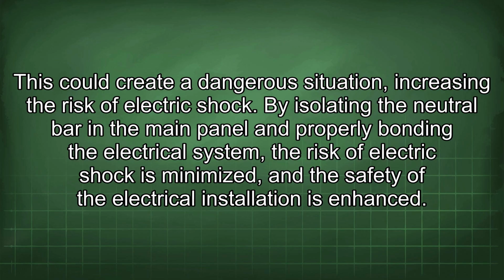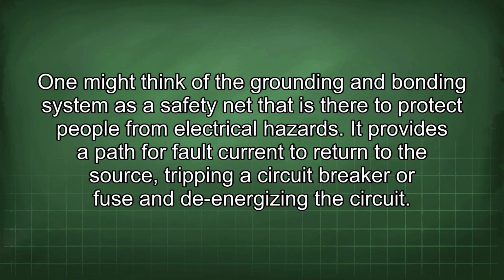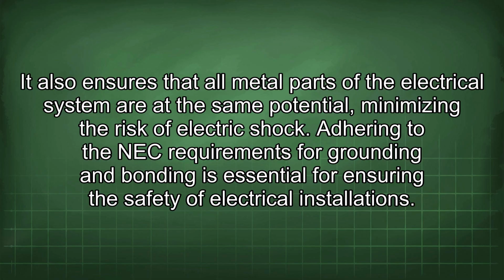By isolating the neutral bar in the main panel and properly bonding the electrical system, the risk of electric shock is minimized and the safety of the electrical installation is enhanced. One might think of the grounding and bonding system as a safety net that is there to protect people from electrical hazards. It provides a path for fault current to return to the source, tripping the circuit breaker or fuse and de-energizing the circuit. It also ensures that all metal parts of the electrical system are at the same potential, minimizing the risk of electric shock.